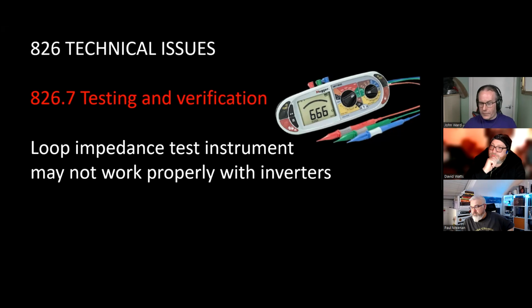And this also fits in with a thing we've seen previously in part 6. Loop impedance testing instruments may not work properly with inverters. You should still test it on there, really, but the results you get may not be what you expect. Now, this is really going to be up to the test equipment manufacturers, because testing things that run off of inverters is going to be pretty much a common thing, because anyone who's got battery storage in a house or a solar PV system already has these inverters. They're already shoving power in, and yet you should be testing with these things there, but some test equipment may not work properly with that.